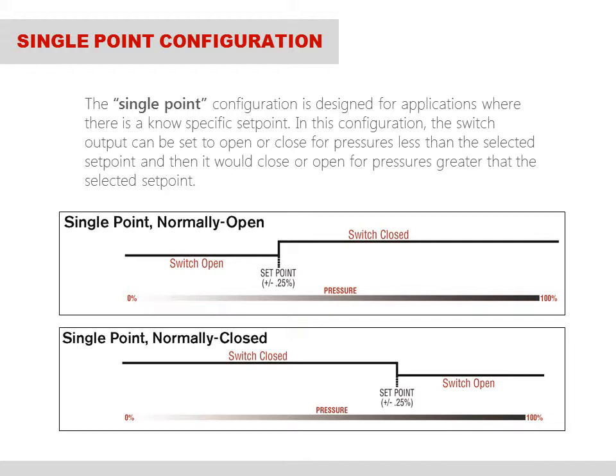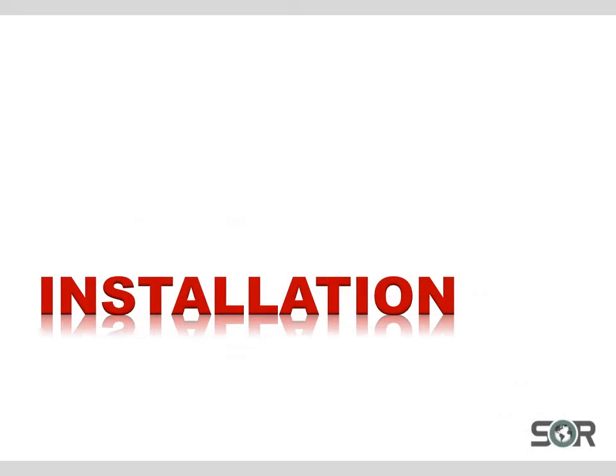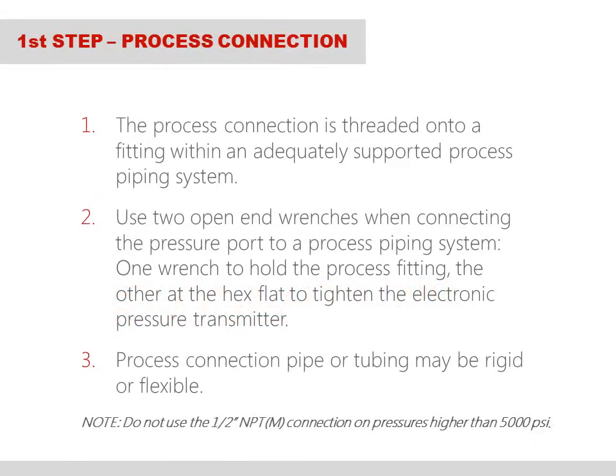So the switch is normally closed and opens when the process pressure rises, and closes again when the process returns to a pressure at or below the set point. The next couple of slides emphasize the proper way to install the 815 PT. The first step in the installation process is to make the process connection.